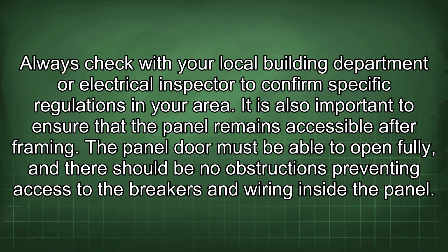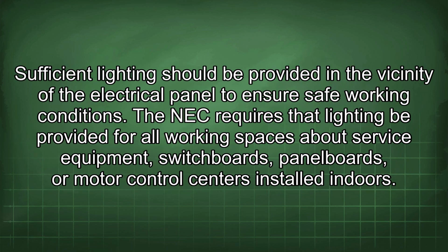Always check with your local building department or electrical inspector to confirm specific regulations in your area. It is also important to ensure that the panel remains accessible after framing. The panel door must be able to open fully, and there should be no obstructions preventing access to the breakers and wiring inside the panel. Sufficient lighting should be provided in the vicinity of the electrical panel to ensure safe working conditions.